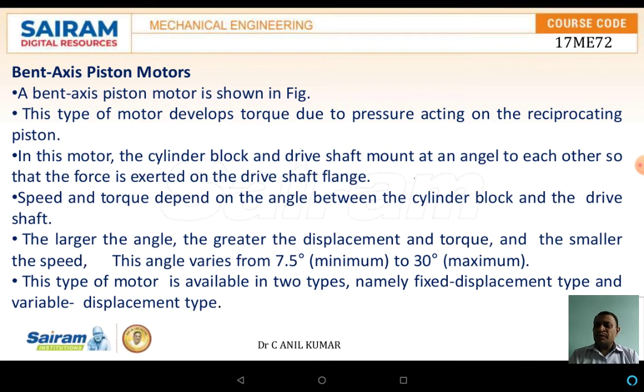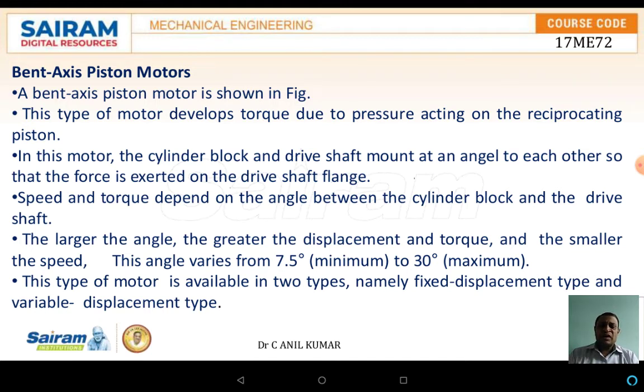The bent axis type motor is another type of piston motor. This type of motor develops torque due to the pressure acting on the reciprocating piston. In this motor, the cylindrical block and the driving shaft are mounted at an angle to each other so that force is exerted on the driving shaft flange. The speed and torque depend upon the angle between the cylinder block and the driving shaft. The larger the angle, the greater the displacement and torque, and the smaller the speed. Normally the angle varies from 7.5 degrees to a maximum of 30 degrees.